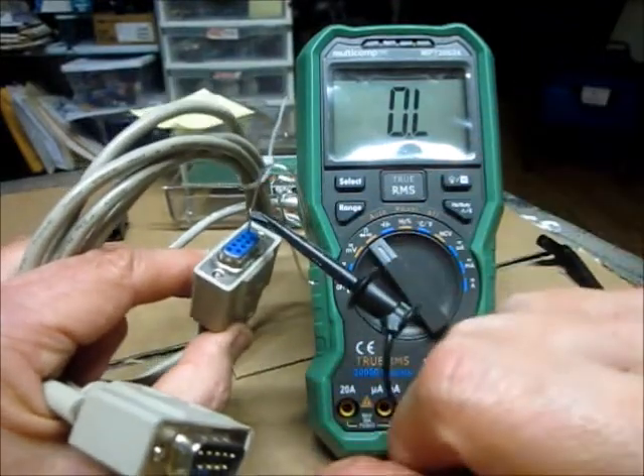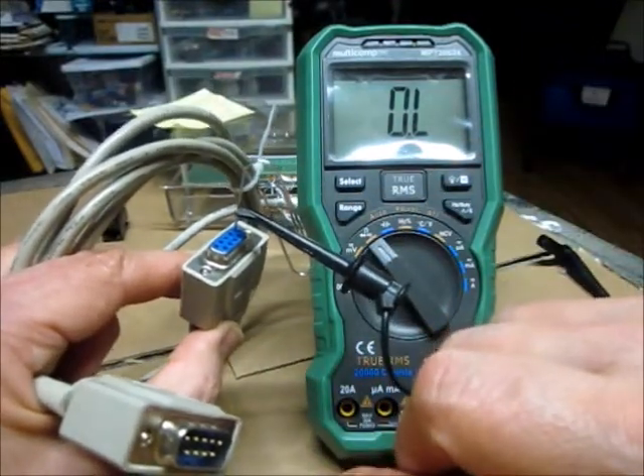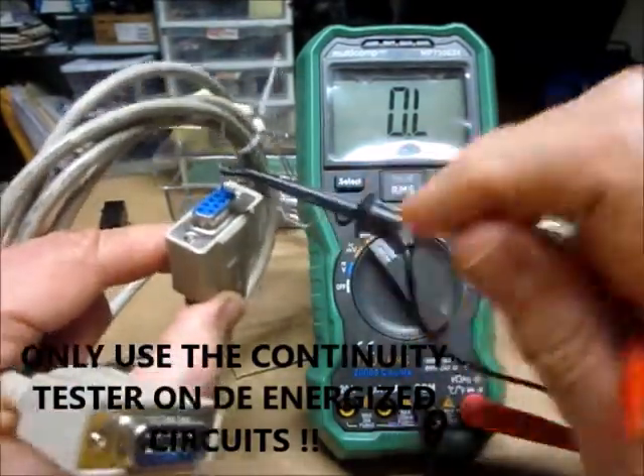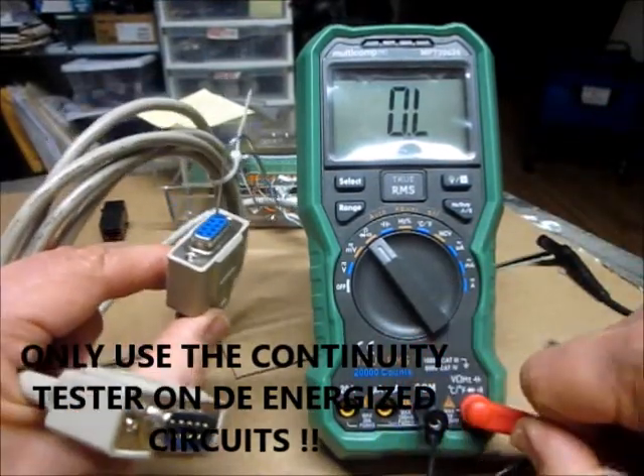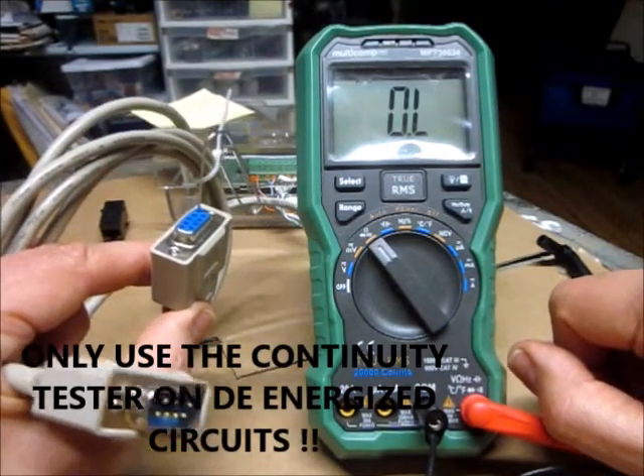In this example too, if you have a suspicion that you have wires going to ground and you're blowing fuses, you can attach the black wire to ground and then just probe around to see if you've got grounded wires. So that's a very helpful and good productivity tool for finding grounds and tracing wires in cables.